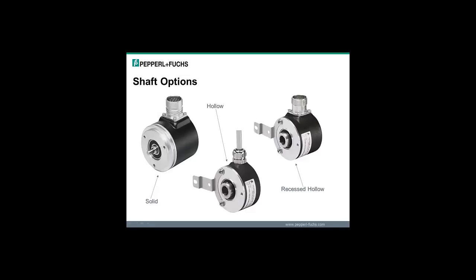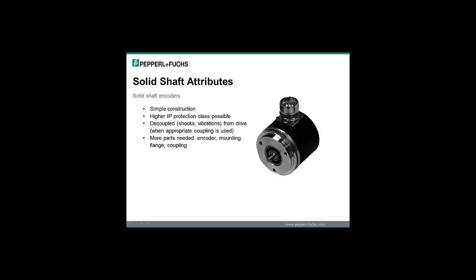The three shaft options are solid, hollow, and recessed hollow. The solid shaft encoder has a simpler construction compared to the hollow and recessed hollow shaft. Higher IP protection is possible. You will need a coupler to attach the encoder shaft to the rotating shaft that needs to be monitored. Overall there would be more accessories that you will need compared with the hollow and recessed hollow shaft encoders.